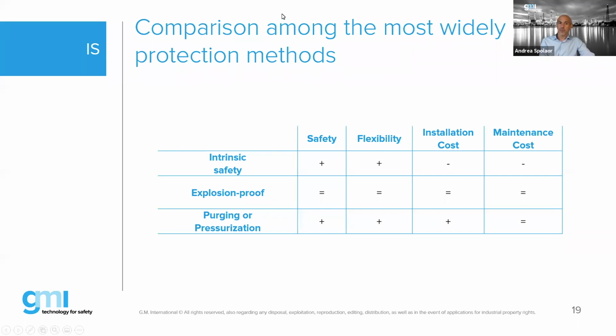However, intrinsic safety, you see here, is more safe because we are controlling the energy, as we said, and is more flexible. The most important thing is also that installation is lower in cost and maintenance is also lower. It's, I would say, a light way to control hazardous area applications, and also assures live maintenance on the application. We are talking about live maintenance for applications in zone 0 also, or Div 1 for the US also.